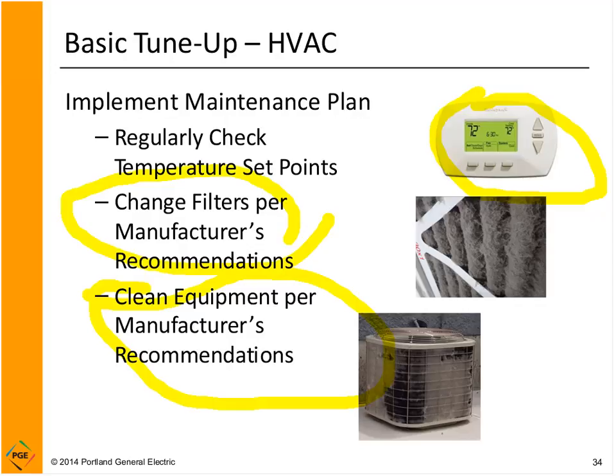This is an example of what's called a condensing unit. It's located outdoors and it's part of what's referred to as a split system. This is the unit that's going to pull heat from your building when you're in air conditioning mode and spit it outside. So in order to do that process efficiently, it needs to be relatively clean. In the process of spitting the heat outside, it needs to move a lot of air through the sides of the unit. If it's dirty, it's going to be moving less air and therefore removing less heat, causing your compressor and your cooling system to work a bit harder.